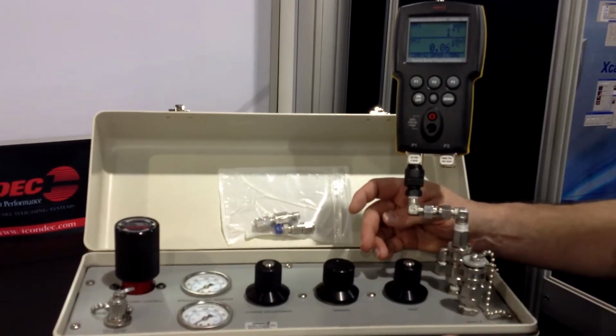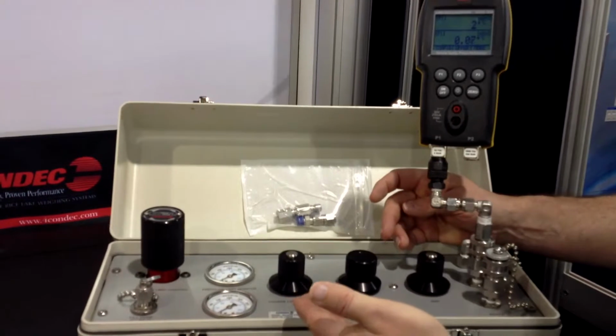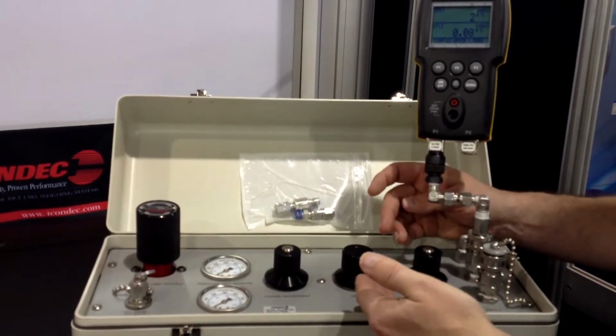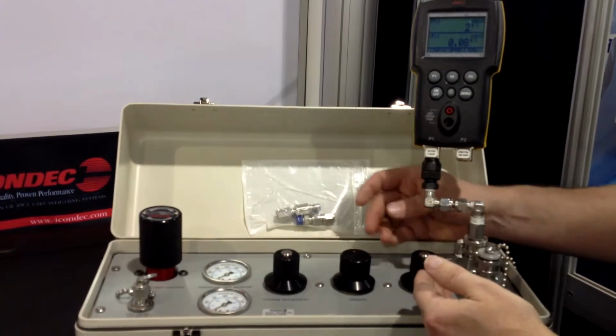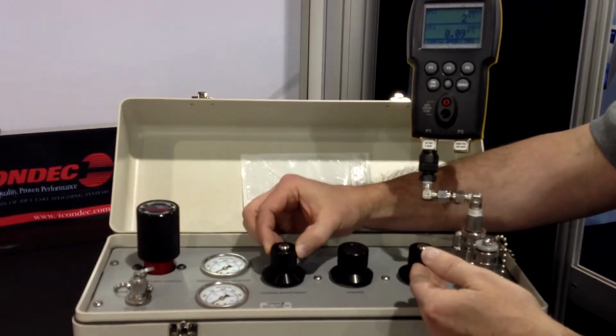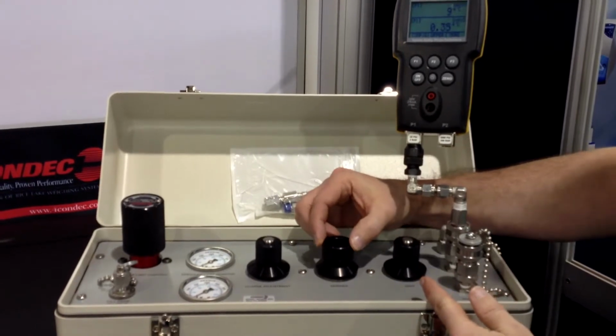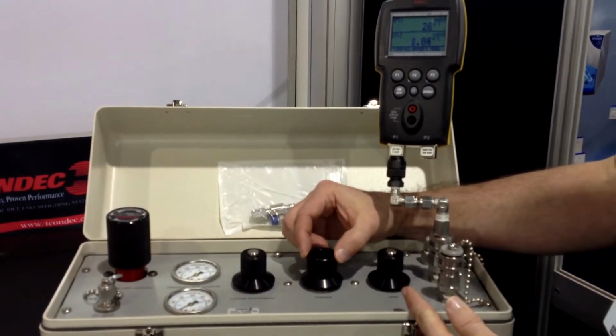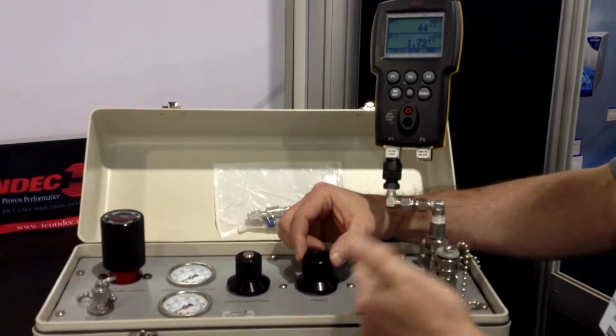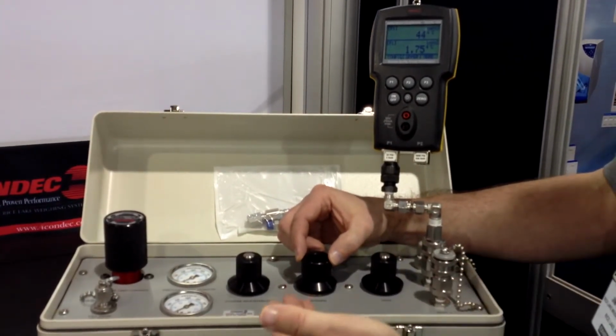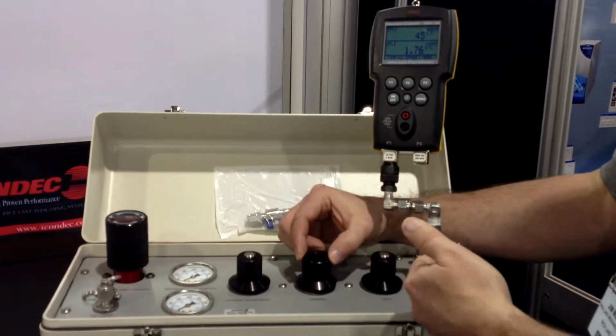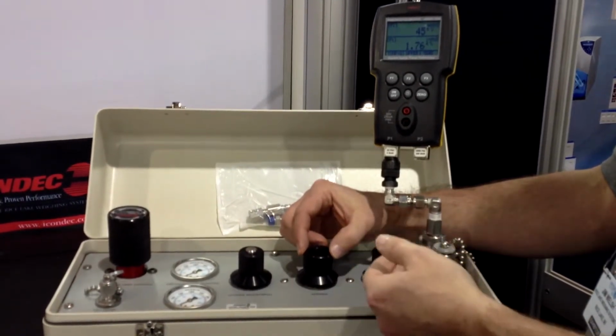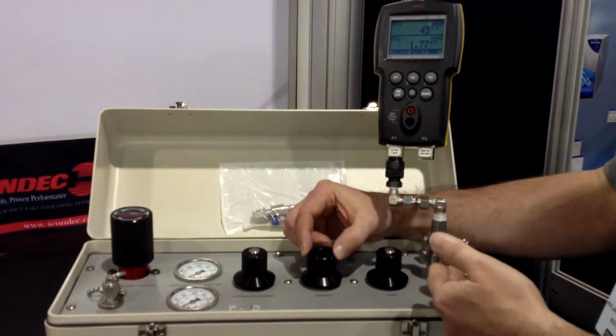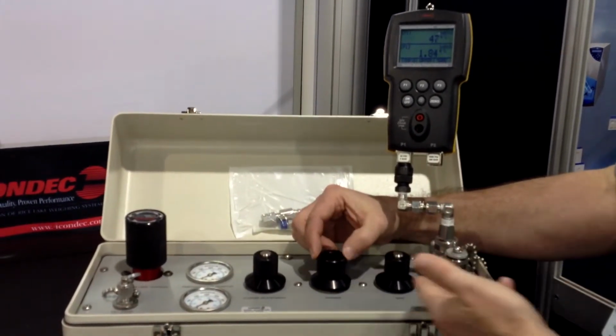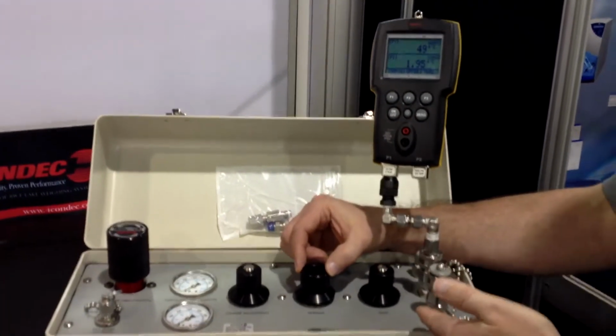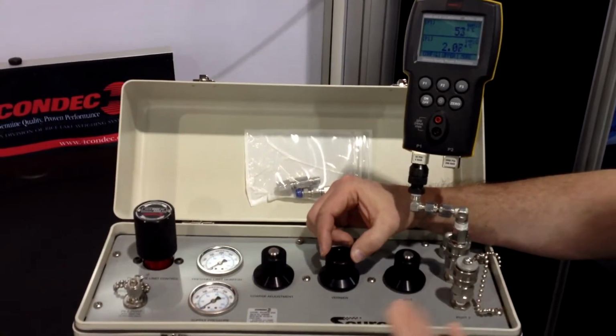Once you've closed your vent valve, let's say you were doing a 10-point calibration. Coming up towards full scale, you're going to want to use your coarse adjustment to get reasonably close to your target pressure. At that point, you would close the coarse adjustment valve and utilize the vernier to bring it right to your point. This allows you to be very precise and accurate so that you don't overshoot your target value. If you overshoot, you're adding an error factor that you wouldn't want. Basically, it's a very simple unit. Anybody can learn to operate it in 20 minutes, or maybe even less.